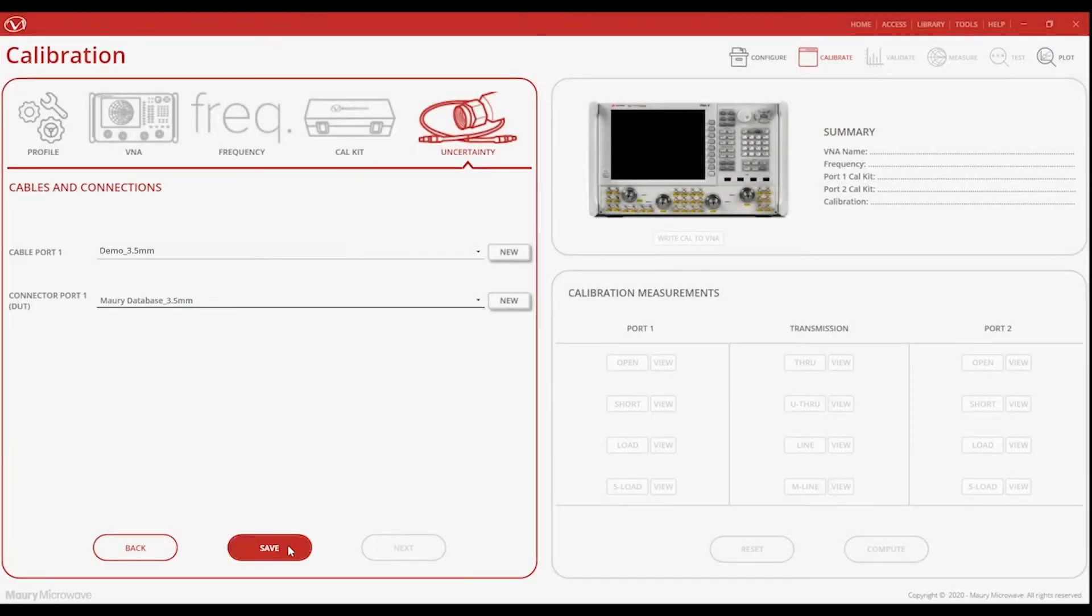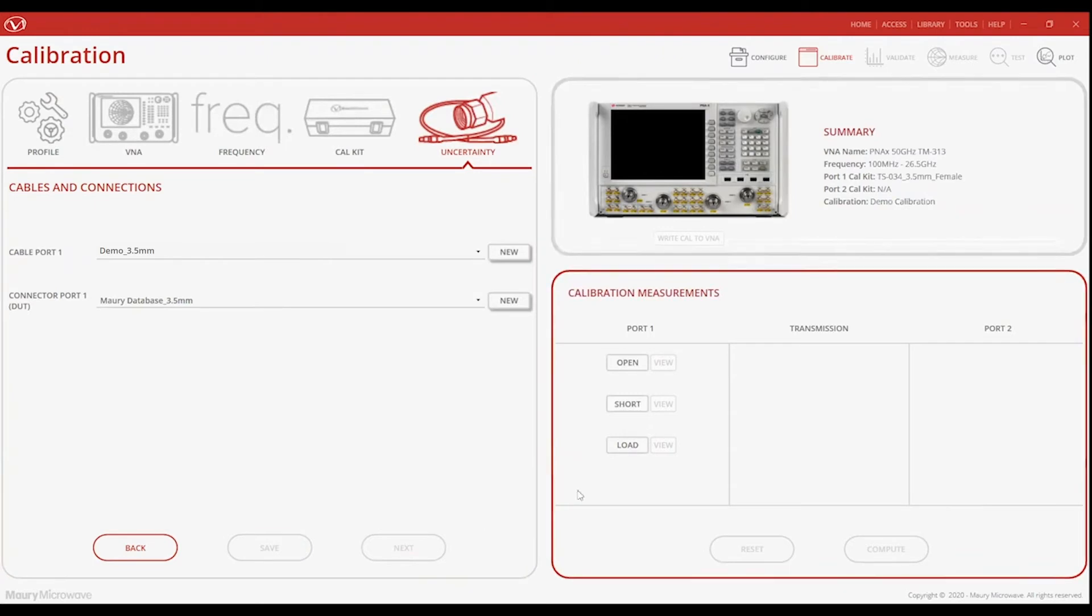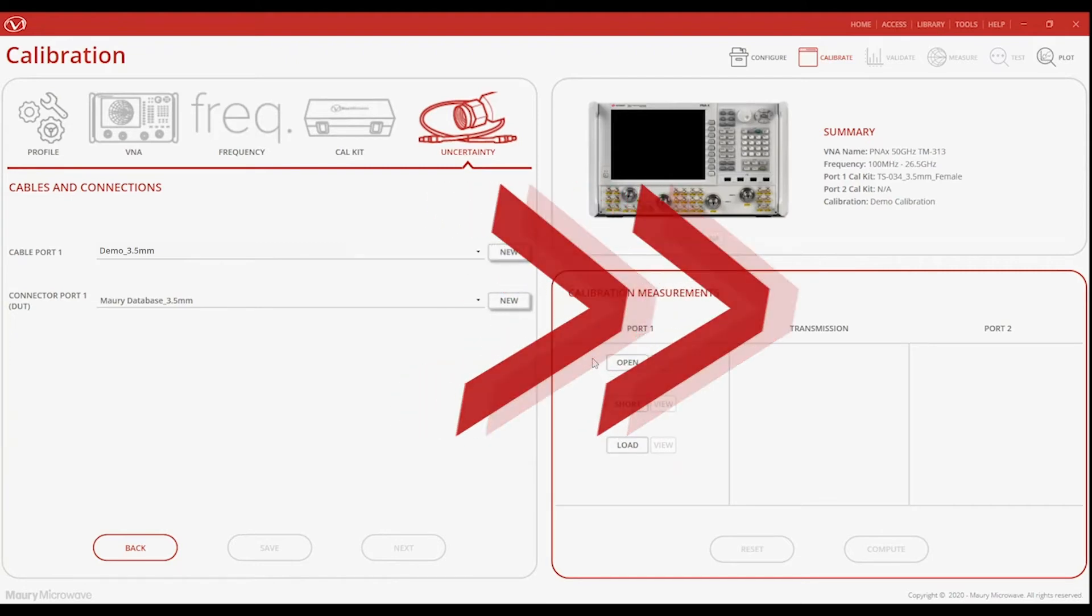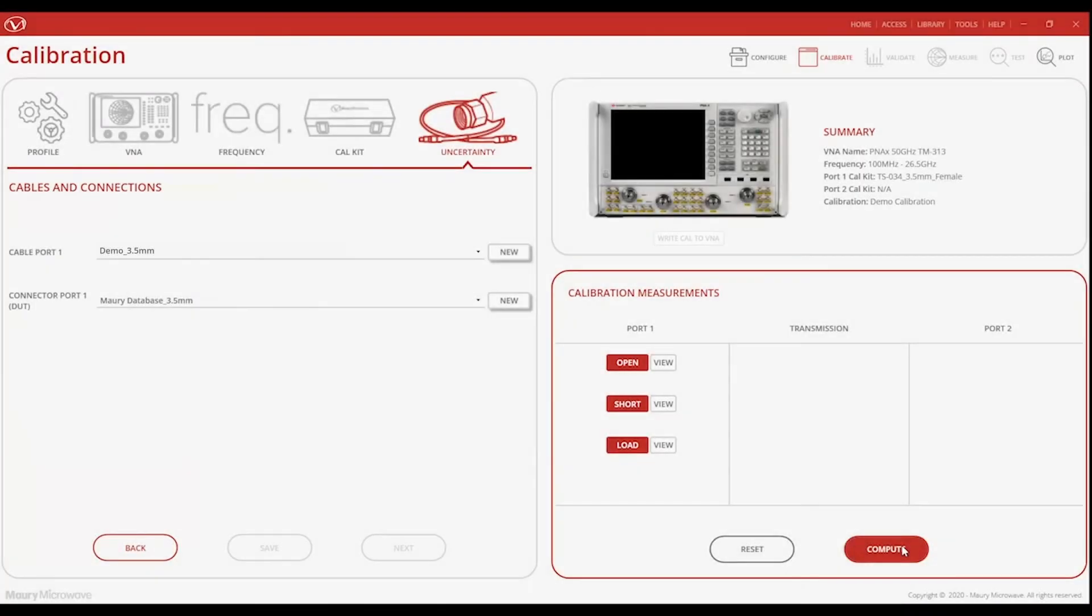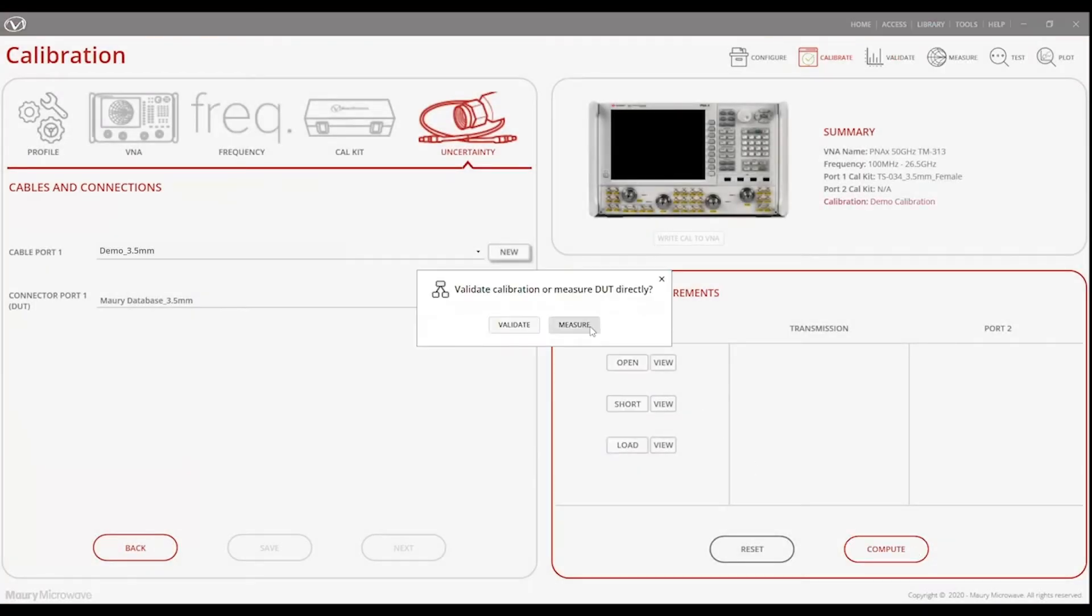Saving the setup creates that project file that can be reloaded later on or shared among colleagues to make sure everyone is calibrating the same way. Insight now prompts us to perform the same calibration defined earlier. In this case, it is asking us to measure an open, a short, and a load. For the sake of time, let's fast forward to the end of the calibration. Once the calibration is complete, Insight prompts us to validate.